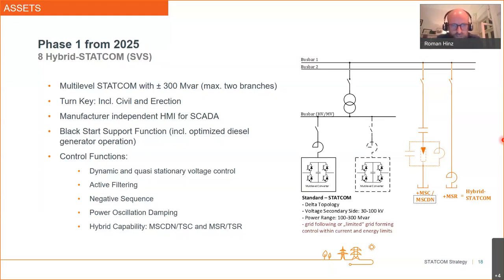For sure, not like an HVDC. We cannot do a black start with the STATCOM. So when the grid, for example, is completely shut down, it is impossible to start this with a STATCOM. But at least STATCOM can support you during this kind of black start. So it means when, for example, a power plant or an HVDC is restarting your grid during a black start, and the voltage comes back to your substation where your STATCOM is installed, we want to use those STATCOMs to stabilize the voltage during this kind of weak grid situation. So it means that we also tender those STATCOMs with, let's say, a weak grid control. So, for example, that the gain is reduced and so on. These are really important topics for us.